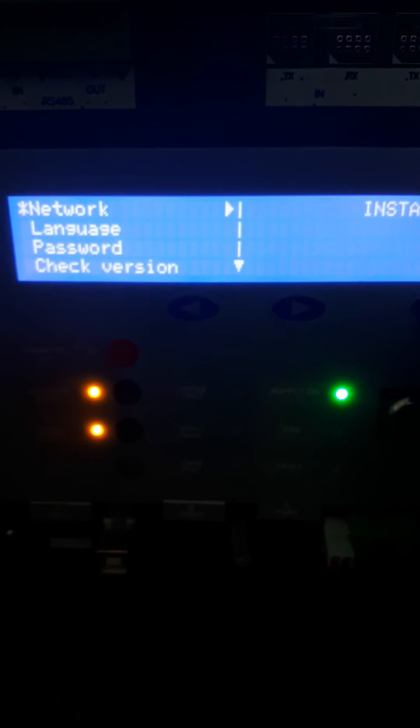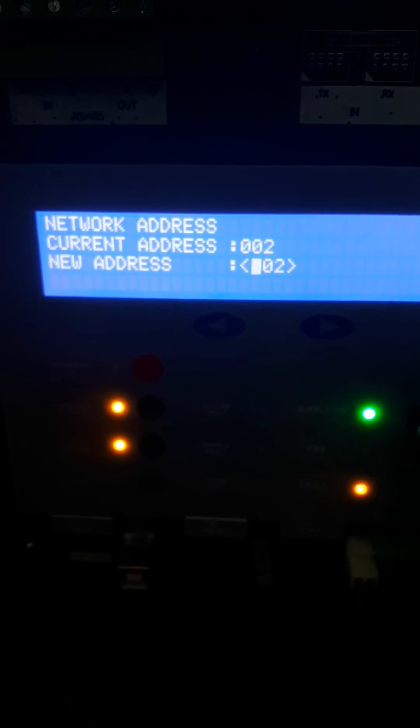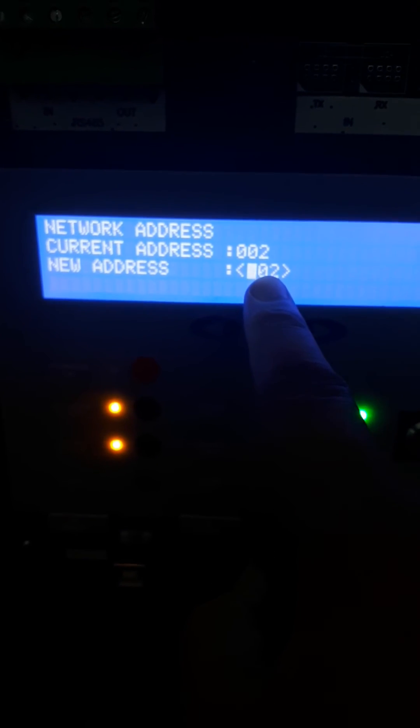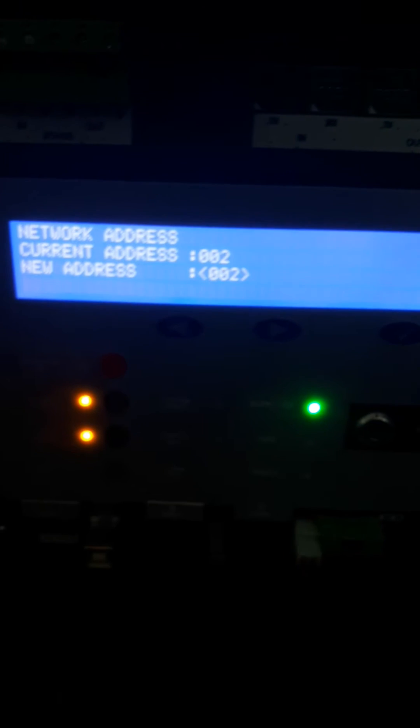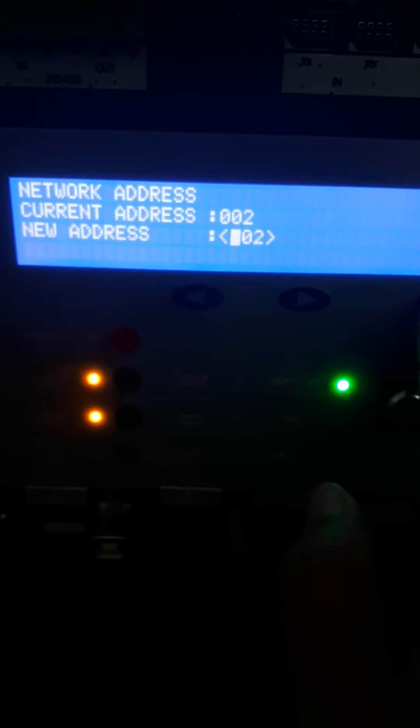Here you will choose network. For network address, you only give addresses to repeaters, not the main panel which is one. This one you will put address two, and the next repeater three, four, five like this.